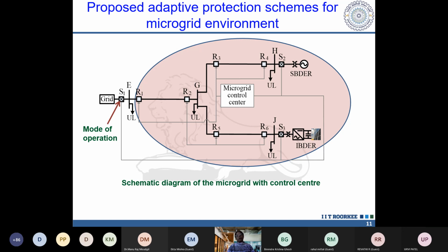So what is islanding? This is also one of the protection issues of the AC microgrid. In an AC microgrid, we have the main grid and the renewables. When a fault occurs on the grid side, the main breaker has to be opened and the rest of the network will be disconnected from the main grid. Now this adaptive scheme, the main microgrid control center, he has developed, and these are some of the relays.